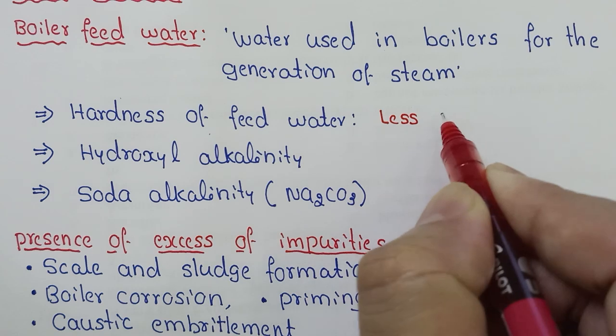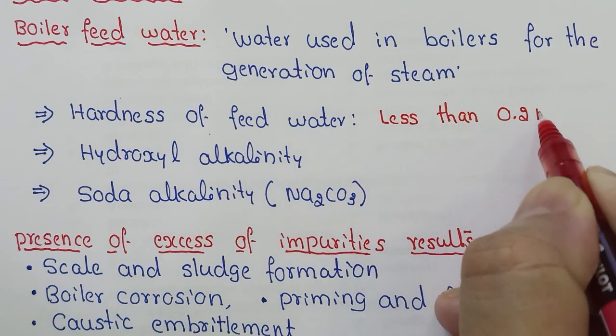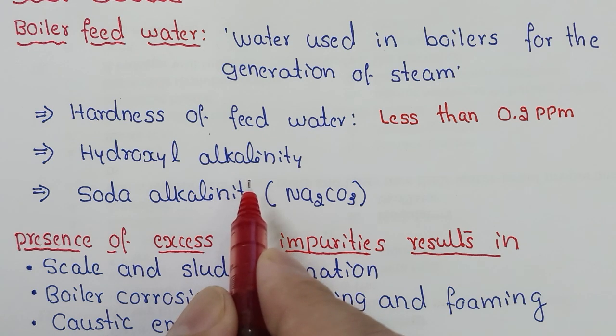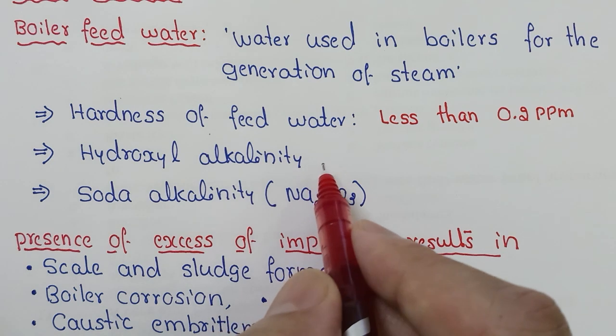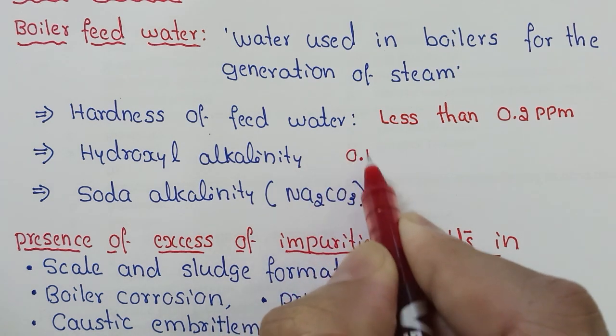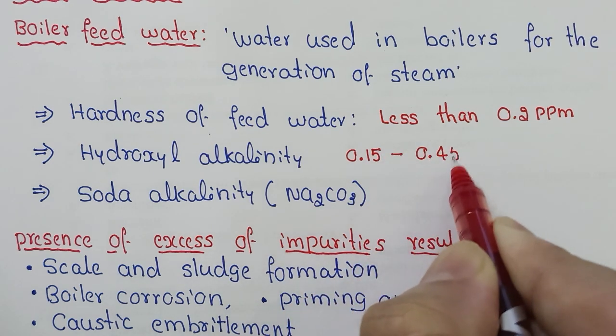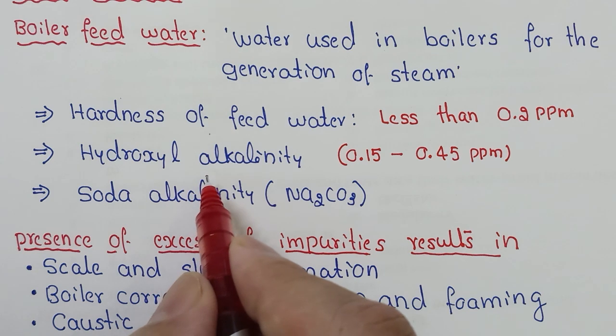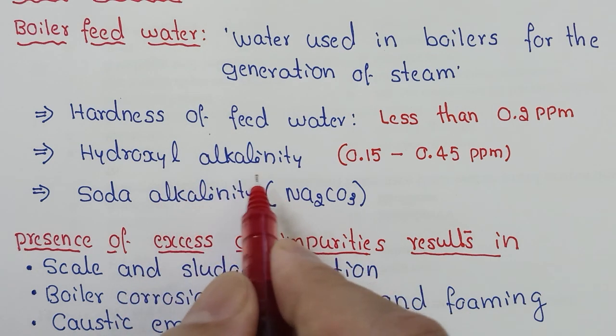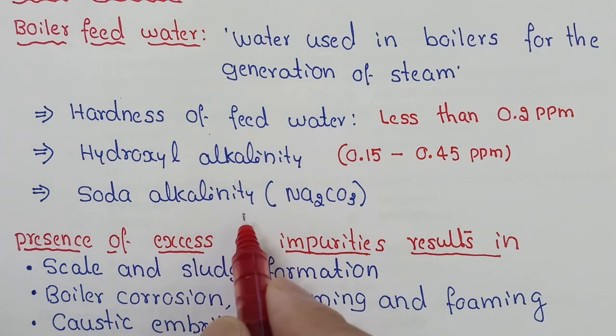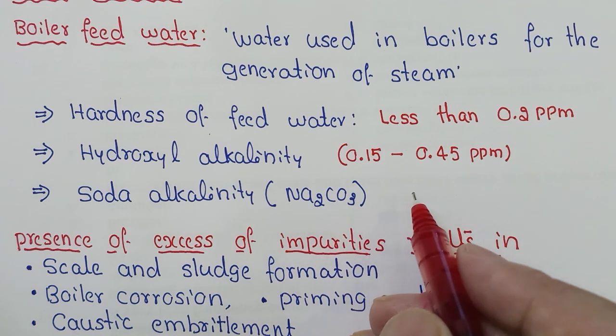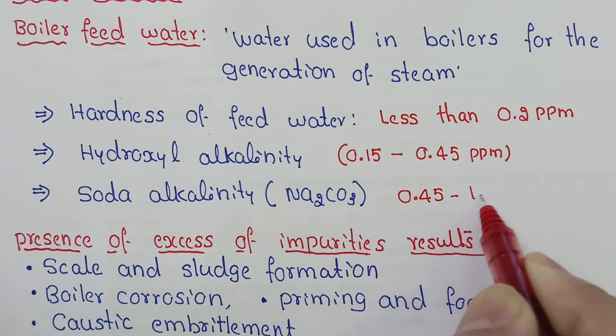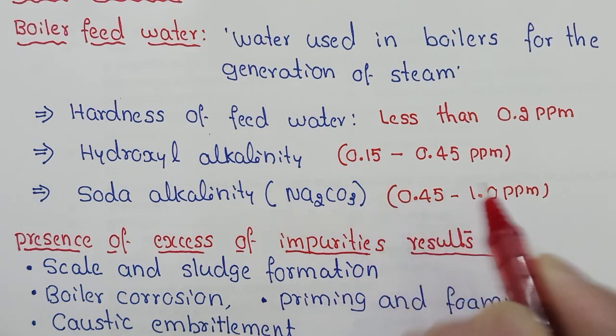The hardness of feed water should be less than 0.2 ppm. Hydroxyl alkalinity — due to caustic soda (NaOH) or hydroxyl ions — should be between 0.15 to 0.45 ppm. This is the tolerable range, and it may be in the form of sodium hydroxide, potassium hydroxide, or any hydroxyl ion. Soda alkalinity, due to dissolved sodium carbonate (Na₂CO₃), should be between 0.45 to 1.0 ppm.